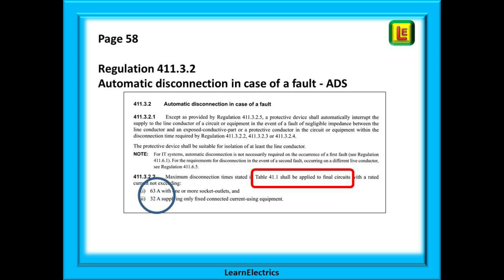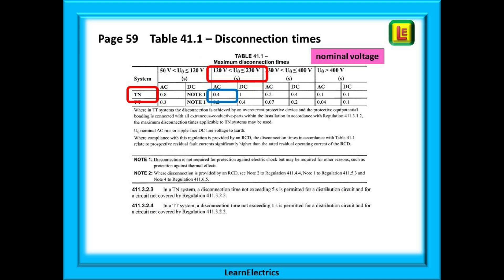The red box here tells us that table 41.1 on the next page only applies to final circuits — we have a separate video on final and distribution circuits, with details and links in the video description. It also tells us that it only applies to circuits up to a certain size of amps, as shown in the blue circle. So let's assume that our circuit is a final circuit rated below the amp limits specified. Table 41.1 will tell us the maximum disconnection time for safety for different nominal voltages and for different earthing systems. Nominal voltage is the name we give to the voltage, not what we actually measure.